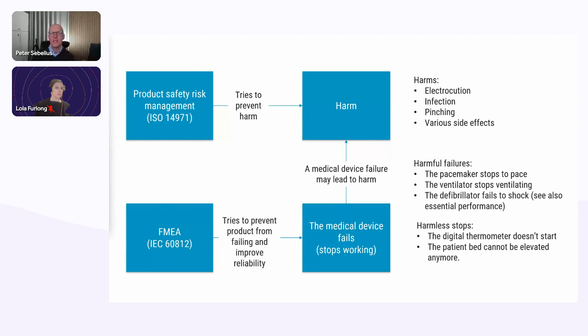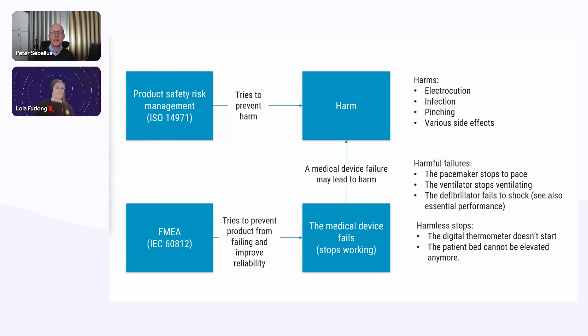And so now we basically have the answer to when you should be using FMEA. Well, if the safety of your device depends on reliability and function, it's a good idea to use FMEA. It would be the case when you, for example, develop a pacemaker. And in the 60601 standard, there is something called essential performance, which is relevant to mention here. What that basically means in layperson's terms is that if you lose a function and the risk is then unacceptable, that is essential performance. And if you have essential performance in your product, then it makes perfect sense to try to improve the reliability and therefore to do FMEA. It's a great tool for that.